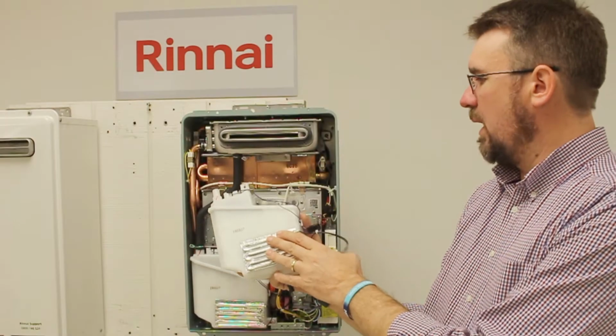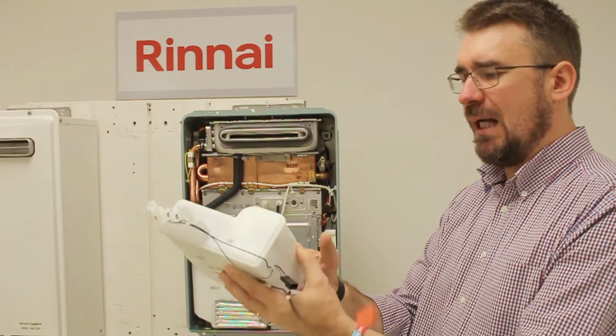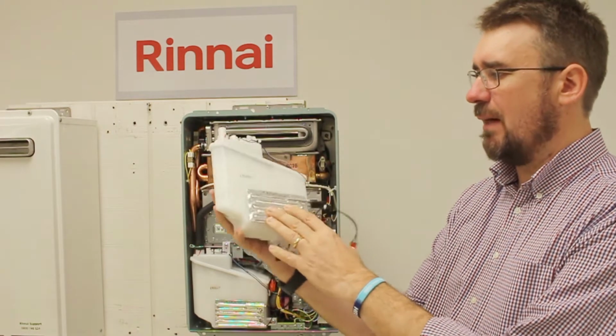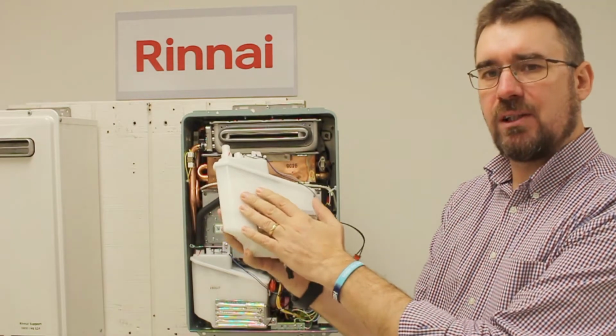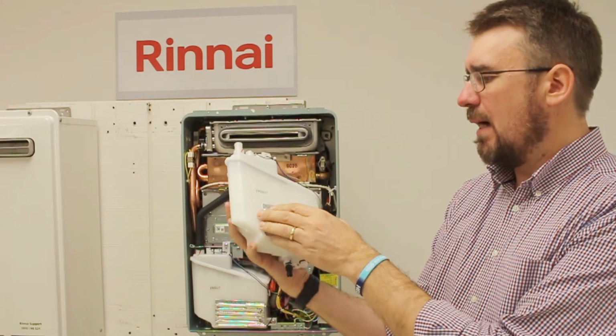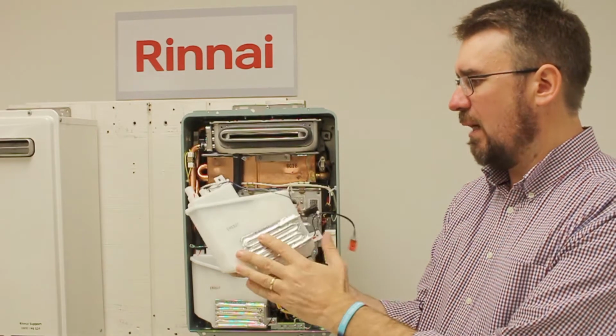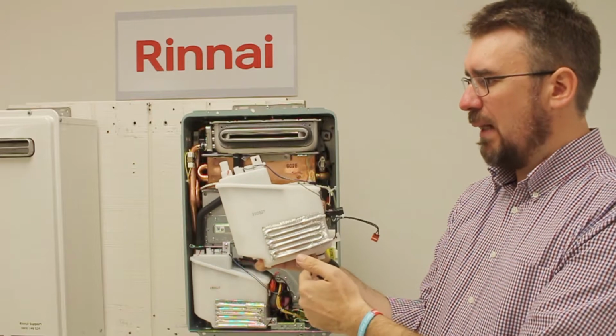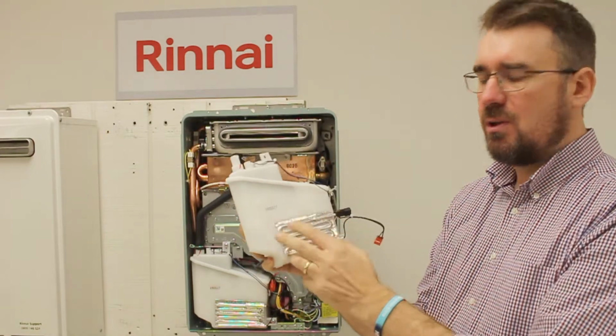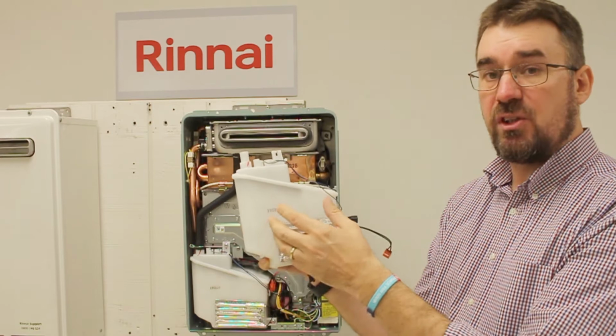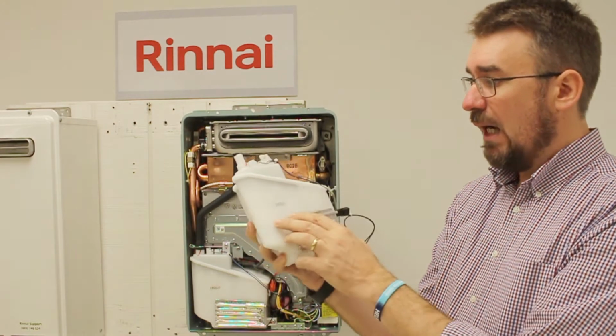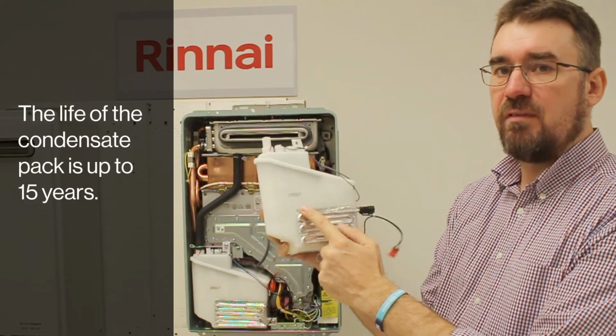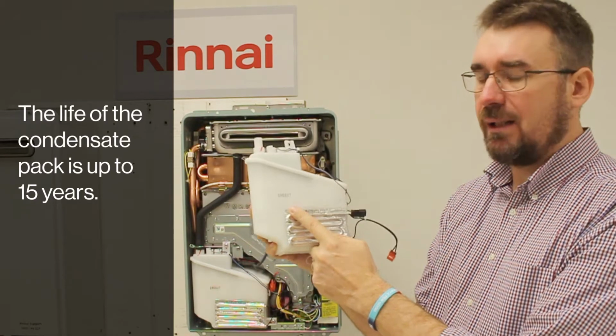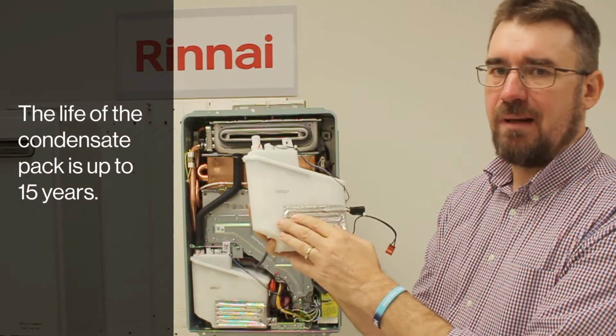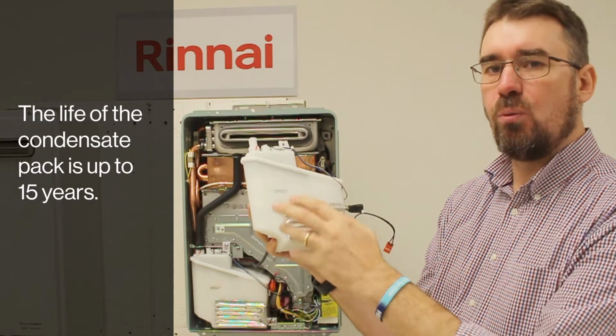Okay, so what we've done here is removed the condensate pack out of a different unit, so we can have a bit of a chat about this. It's quite a different thing that's not really been seen in many Infinity units before. What we've got here is a condensate collection and treatment pack. It's completely sealed, so it's not a user serviceable or even a service person serviceable item. The contents are in here for the life of the unit or the life of the pack, and that works out to be around 10 to 15 years with normal domestic use.